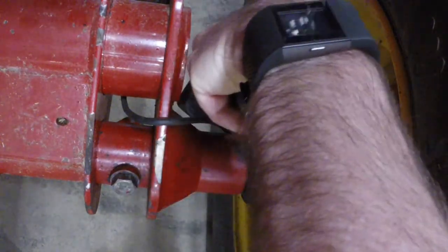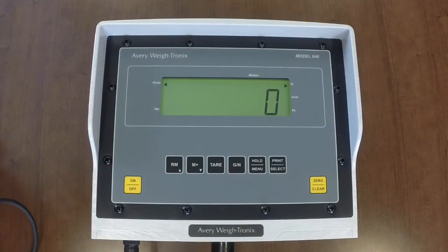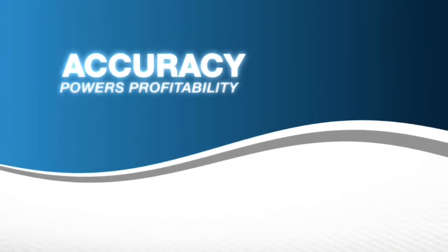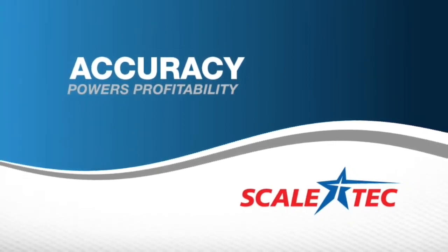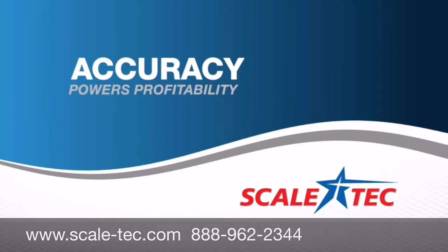After determining if the weigh bar is good or bad and fixing any bad spots in the wiring, disconnect that weigh bar and connect a different one into the indicator or junction box. Troubleshoot each weigh bar individually the same as the first. If you have any questions at all, please don't hesitate to contact Scale-Tec. We are always happy to help you with the steps for troubleshooting. For more in-depth guidance, please refer to our troubleshooting guide found on our website under the training and support section.